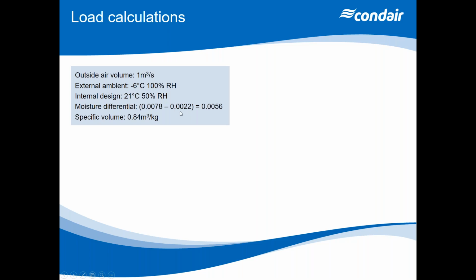So from our psychrometric chart, we can then establish that there's a moisture difference between those two conditions. And here it's pretty straightforward. Moisture content at -6 at 100% is 0.0022 kilograms per kilogram, as against 0.0078 at 21 at 50. So I've got a difference there of 0.0056 kilograms per kilogram of moisture that I need to add to the air to get me to my condition. And I'm also going to want to know the specific volume from the critical part of the process, not necessarily your supply air temperature, because those two could be different.